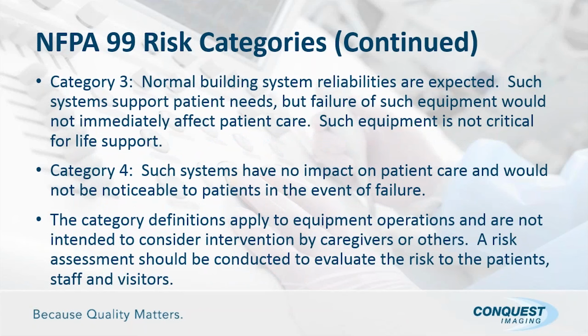Category 3, these are just normal building systems where the reliability is expected to be what a normal computer would be in an office building. There's still equipment that supports patient needs, but failure of such equipment would not immediately affect patient care. And it's definitely, the last point, not critical for life support. So important to know. Category 4 have no impact on patient care, and patients would not notice or have any discomfort in the event of a failure. Now, these categories apply to equipment operations and are not intended to consider intervention by caregivers or others.